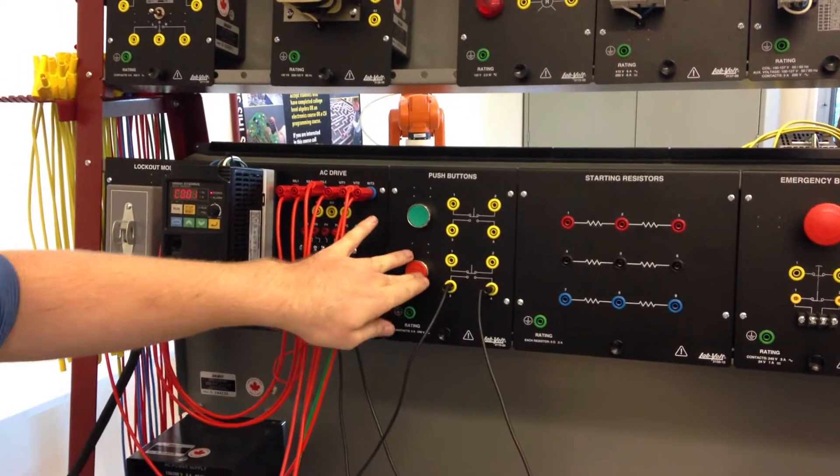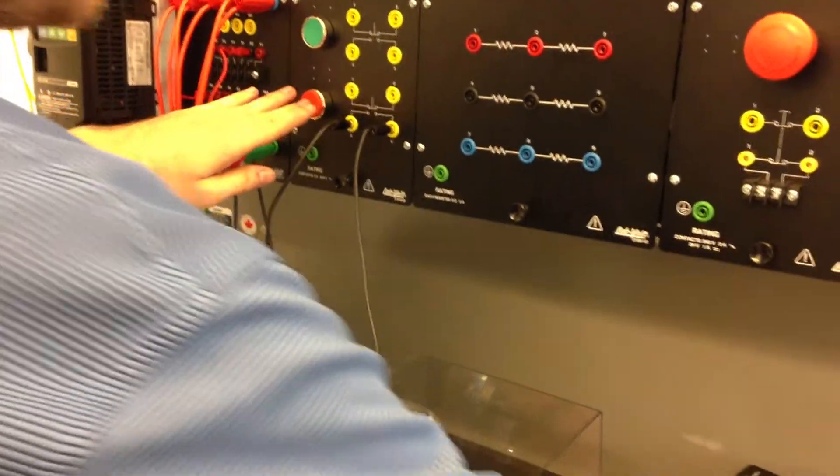So, I don't know if you can hear that, but when I push it the DC Braking is active. So if I go ahead and spin this, it spins free, hit the button, it's much harder to press.